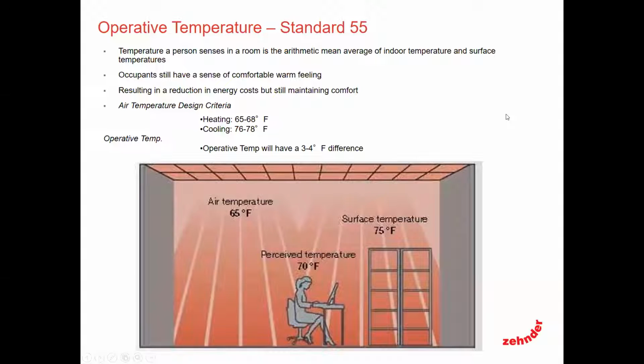So what that means is when we manufacturers design radiant-based systems, in heating mode, we will design an air temperature somewhere between 65 to 68. And in cooling mode, we will design somewhere between 76 to 78. And then generally, based on the mean radiant temperature, the amount of active surface area you have versus uncontrolled surface area, you will generally find it somewhere between 3 to 4 degrees lower or higher than that.